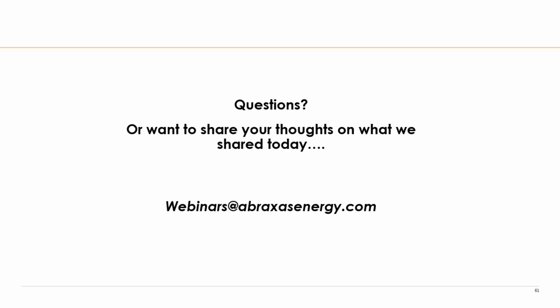Okay. Under what conditions is this recommendable? For example, if you have a 3 cents per kilowatt hour utility rate, it probably is not a good solution. Do you have any rules of thumb where it applies and where it does not? Sure. 3 cents per kilowatt hour is very, very low. Generally, most markets that are applying this as a retrofit are around 13 cents per kilowatt hour. Even in areas with very low cost of electricity, if it's a new construction project, you can see first cost capital savings and then ongoing maintenance savings, or at least net neutral versus the maintenance costs of cartridge changeout. So new construction, I'd say it's nationwide. Retrofit, you are going to want to be focused on utility rebates and high cost of electricity.